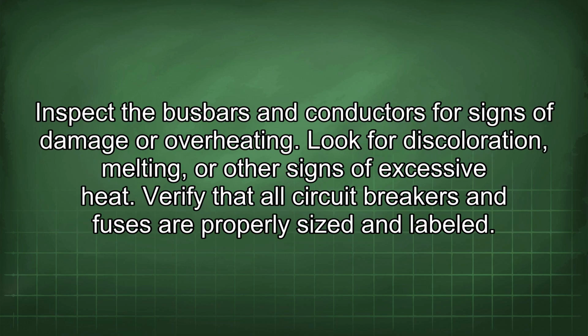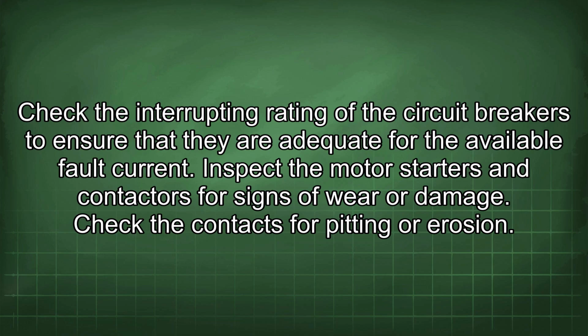Inspect the busbars and conductors for signs of damage or overheating. Look for discoloration, melting, or other signs of excessive heat. Verify that all circuit breakers and fuses are properly sized and labeled. Check the interrupting rating of the circuit breakers to ensure that they are adequate for the available fault current.